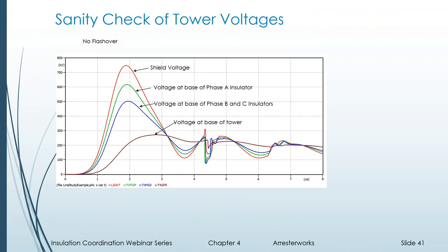What I always do is start low and impulse at higher and higher currents. I don't impulse the arrester; I impulse the shield wire with higher and higher currents. Remember, we're not looking for a voltage on the shield. If you think back to a substation, we put a voltage on the front end of the substation that's coming down the line. We don't really care what kind of current's behind it. We just care that there's a voltage surge coming into the substation.